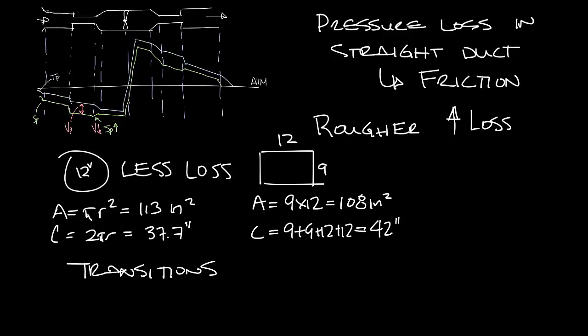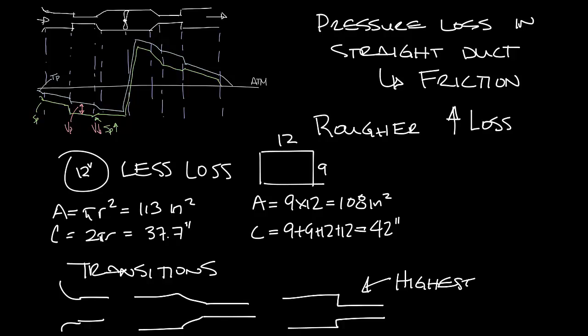Inlet and outlet transitions will affect pressure loss as well. The more gradual the transition, the lower pressure loss. So a bell mouth is probably the best and then a slight angle down to the smaller ductwork and then the worst is going to be just a hard transition from one to the other and that will have the highest loss.